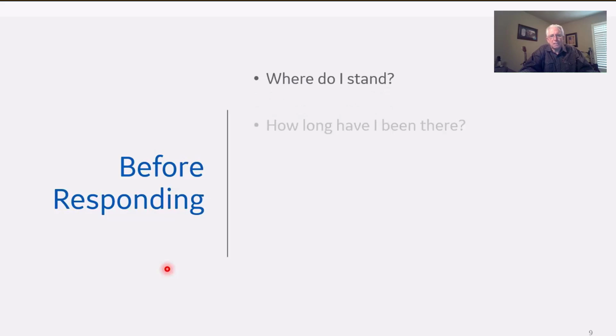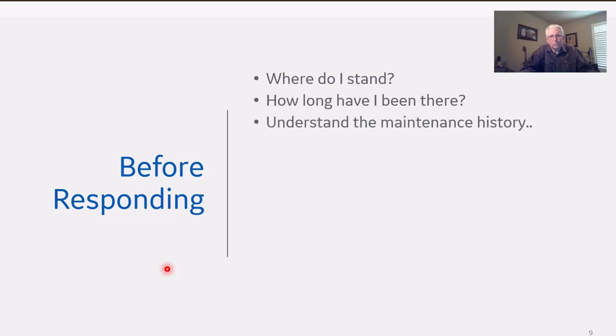So before responding, you've got to know where you stand. How long have I been there? Some of these questions we put up last week. Understand the maintenance history on the transformer. One of the reasons I bring this maintenance history up is because many of you on this very call have probably had transformers in the past that had a repeated problem. The problem was repaired, and guess what? It came back. You ended up with the same issue all over again. It could be a design problem with the transformer, it could be the first time this problem happened it wasn't repaired correctly, or maybe something was over-tightened or broke, or there's a ton of avenues you can go down from a why standpoint.